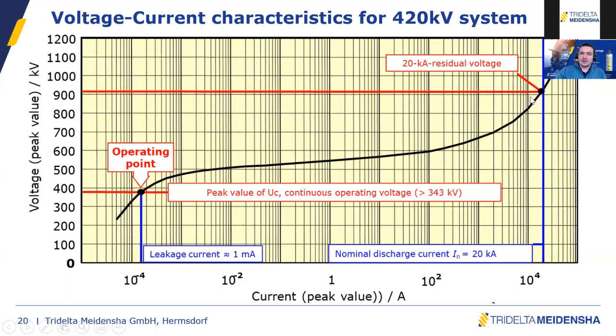And this curve is important because for each MOV block, there is a ratio between the protection level and the rated voltage of the arrester. To make it simple, this ratio is between the overvoltage protection and the operation behavior. This ratio is in the range of 2.2, 2.4, depending on the block size and the block characteristic. This is one of the keys when you manufacture blocks, because everybody would like to have a high TOV value, so that the surge arrester can withstand high TOV with a very low protection level. But of course, this is not possible.